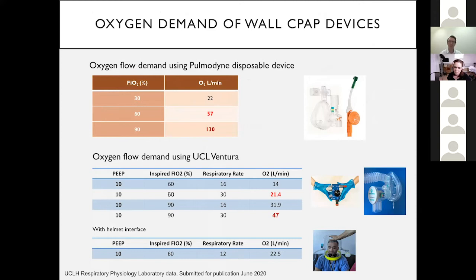Compare that to the UCL Ventura device, and you can see a marked difference between the flow demand, such that at an FiO2 of 60% and a high respiratory rate, only 20 liters or so a minute of oxygen is required.